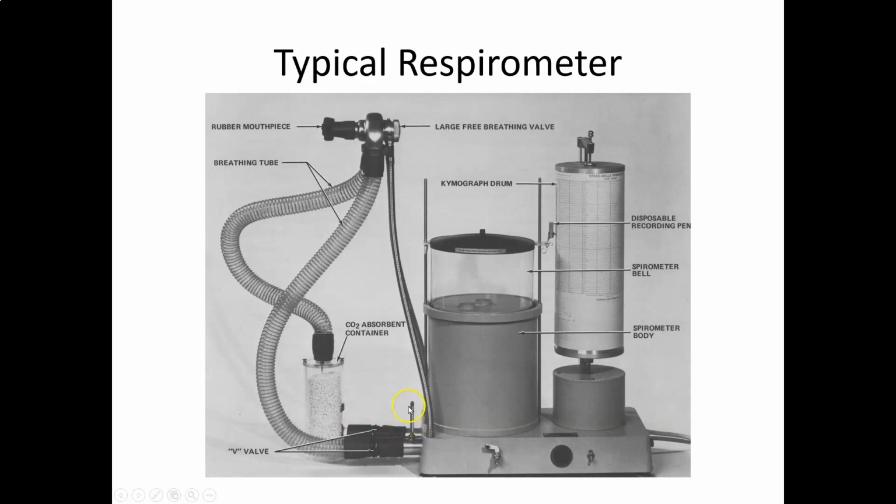The BT is body temperature. The P is pressure. We do not have a humidity gauge here, but we would have to measure the relative humidity and the barometric pressure. You'd measure the barometric pressure with a barometer. You can get that online pretty much anywhere nowadays. There are a lot of local weather stations. If you look hard enough, you can find the barometric pressure in the area you're at. We just want to standardize everything to one atmospheric pressure, which is 760 millimeters of mercury.